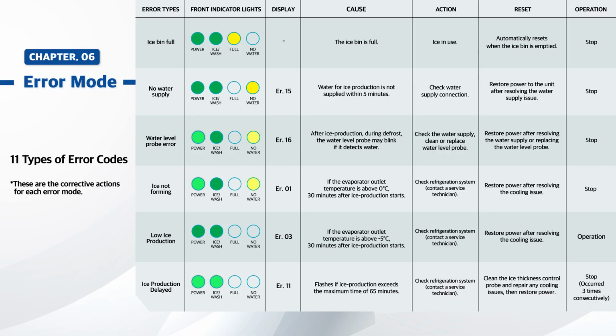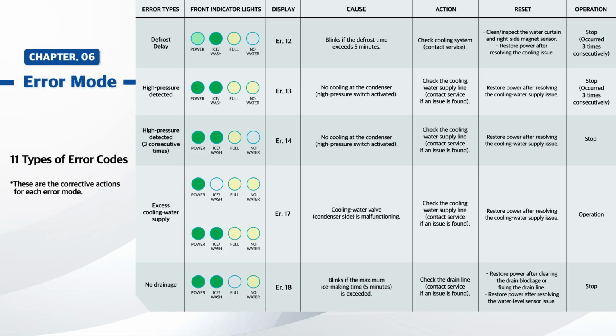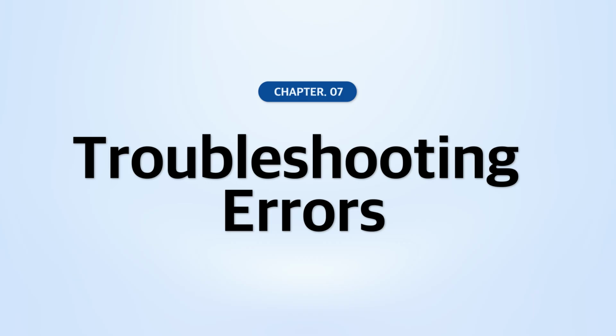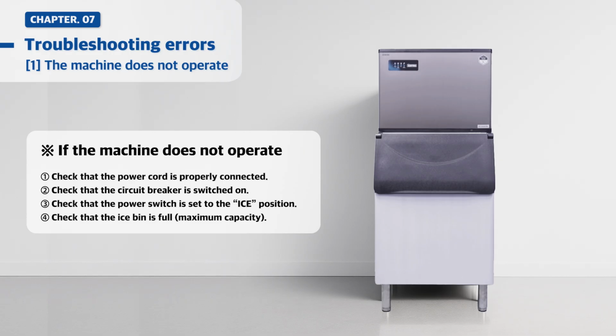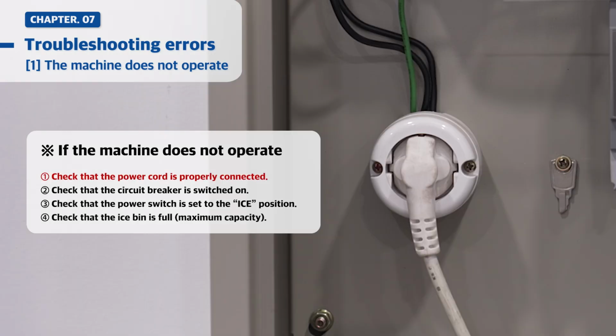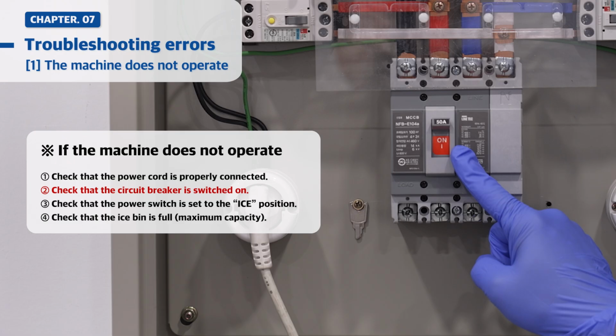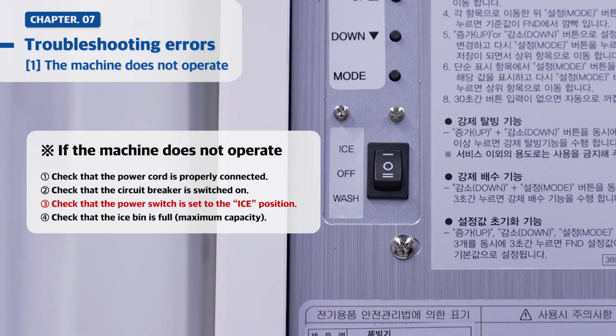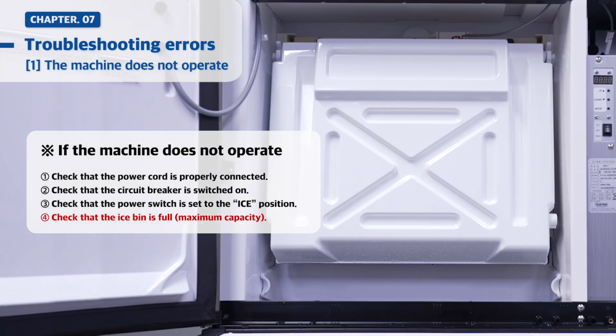These are the corrective actions for each error mode. If the machine does not operate, check that the power cord is properly connected. Check that the circuit breaker is switched on. Check that the power switch is set to the ice position. Check that the ice bin is full.